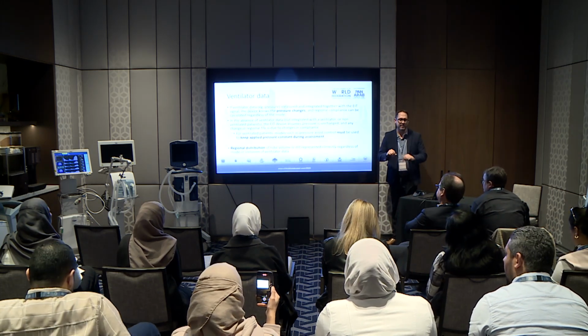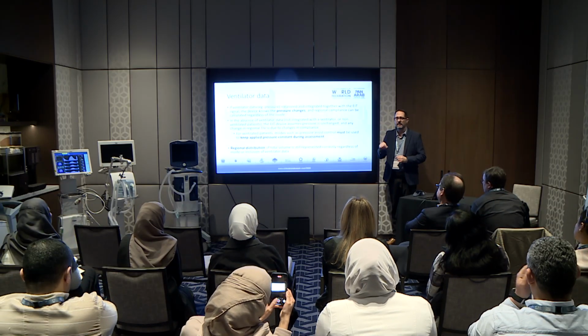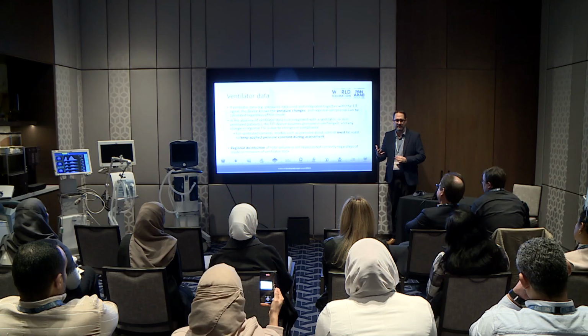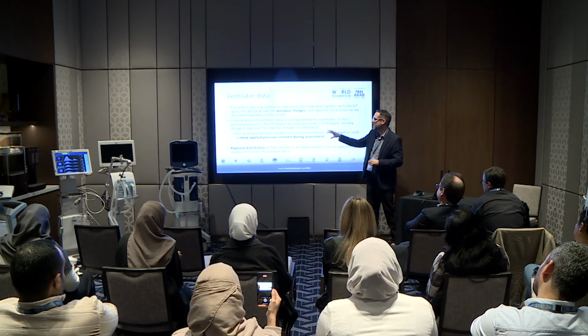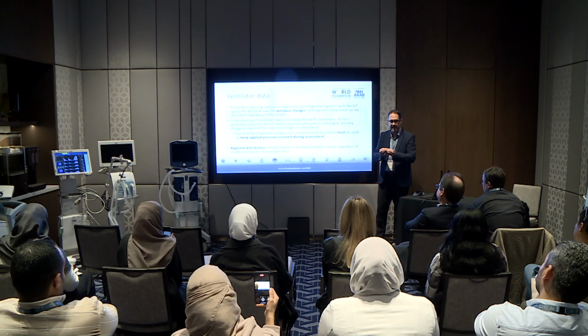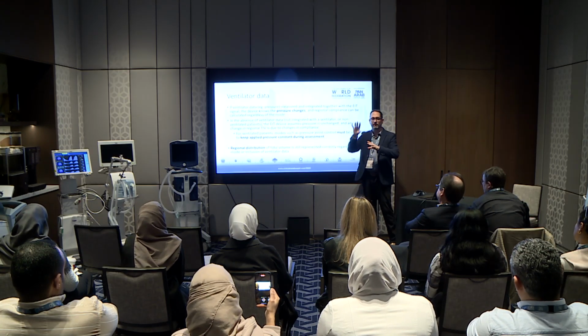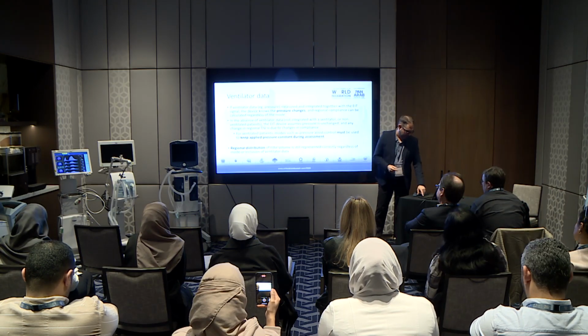I will have to control pressure because it assumes pressure is not changing. Any change in the height of impedance reflects as a change in compliance, and it assumes the pressure is not changing. So you have to use pressure control if you're not using directly measured ventilator data with EIT. And during your PEEP maneuvers, pressure control would have to stay the same. It's very important if you want accurate measurements of compliance.